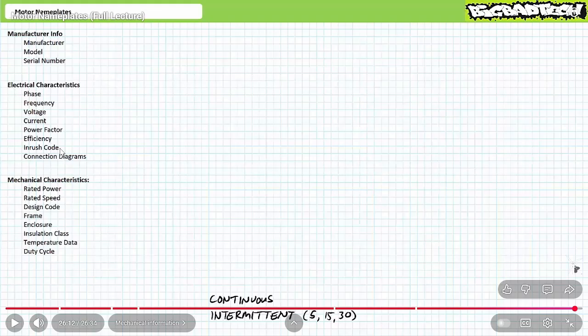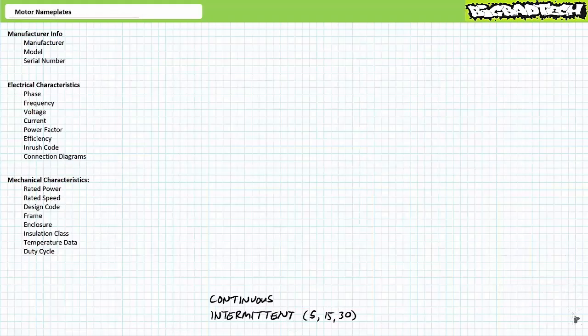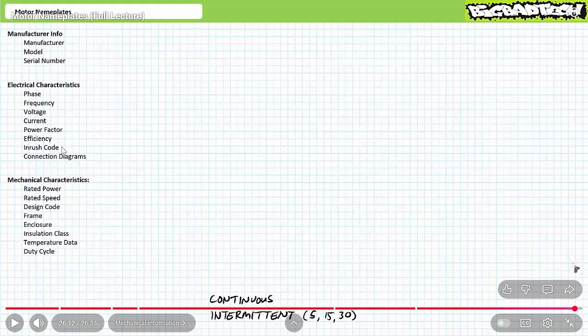I've hardly ever paid any attention to the inrush code, but you should, because that code, if it's not a small one, you might have to increase the size of your breaker, or your circuit breaker in front of your motor starter, and that is important.